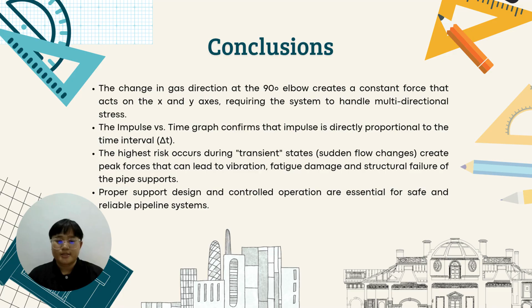Next is practical recommendation. First is to implement gradual valve actuation. We should know that valves should be opened and closed slowly to protect the system. By controlling the time interval, the kick or impulse force is spread out. This will prevent the sudden shock that can cause damage to the elbow.